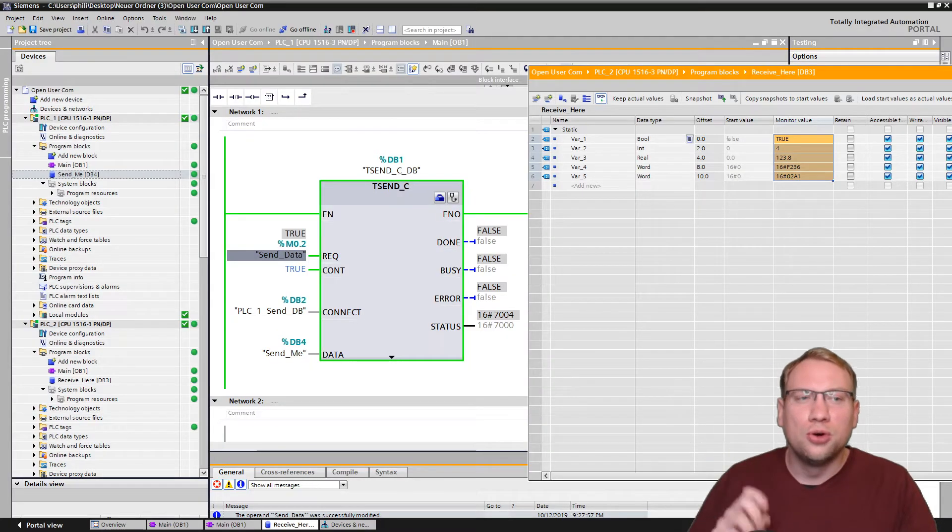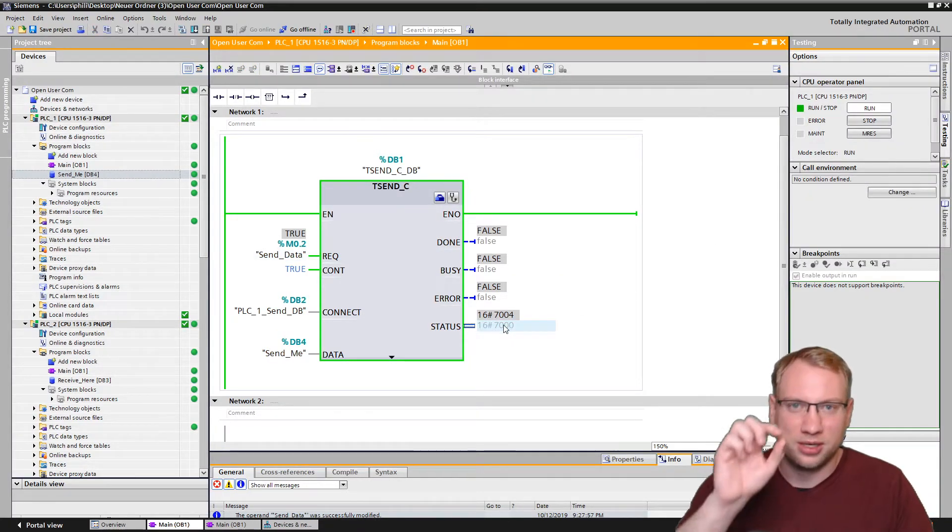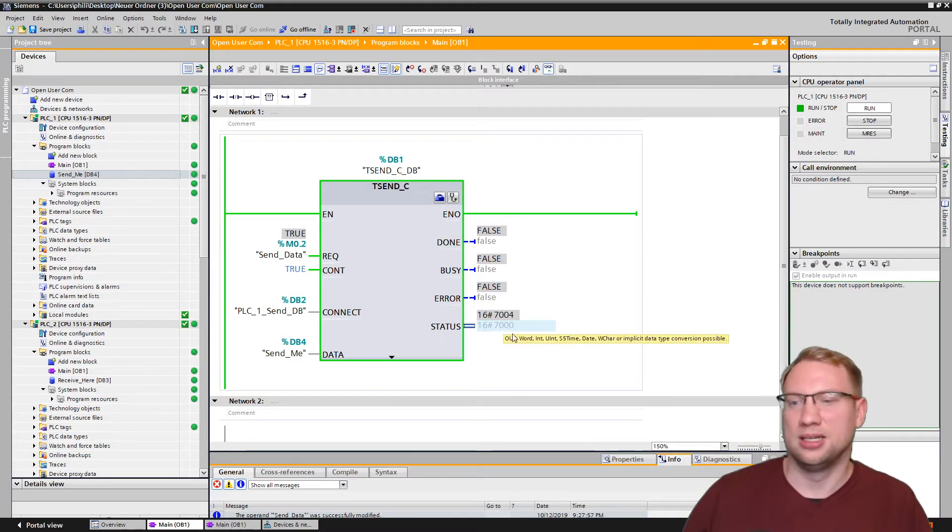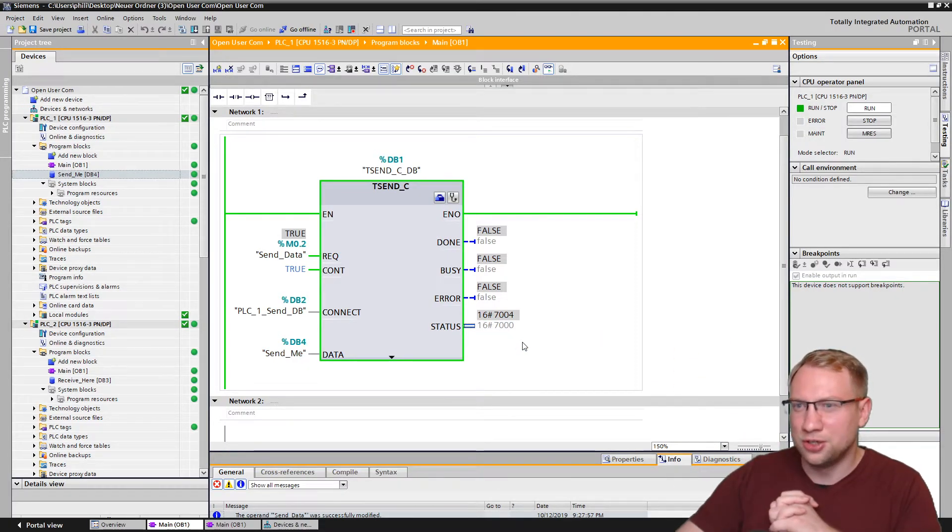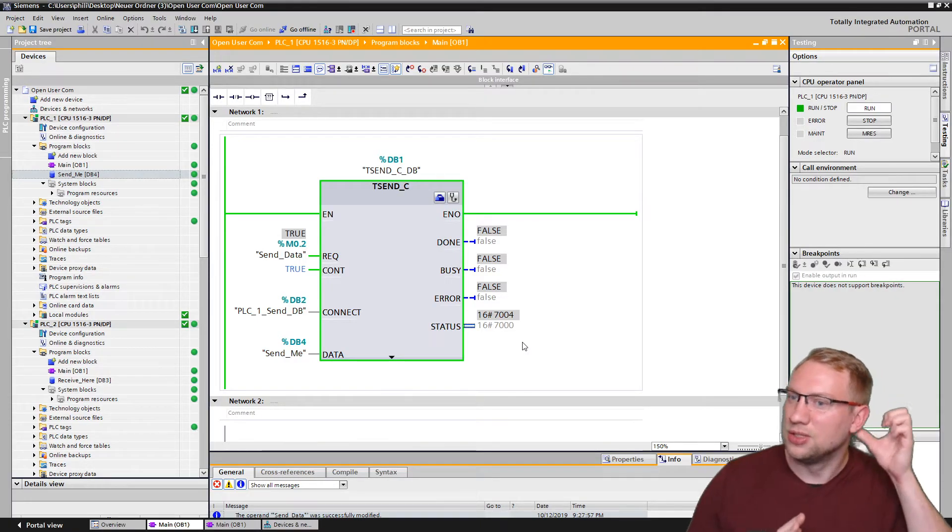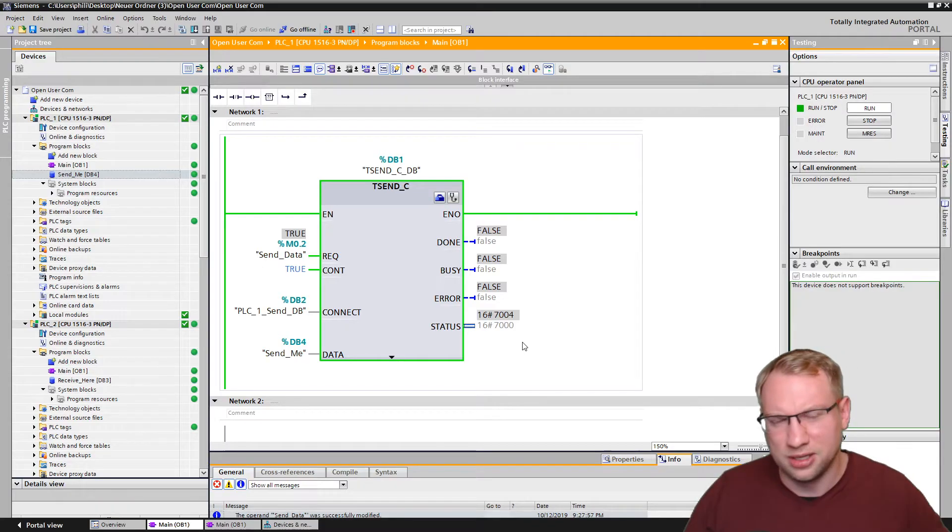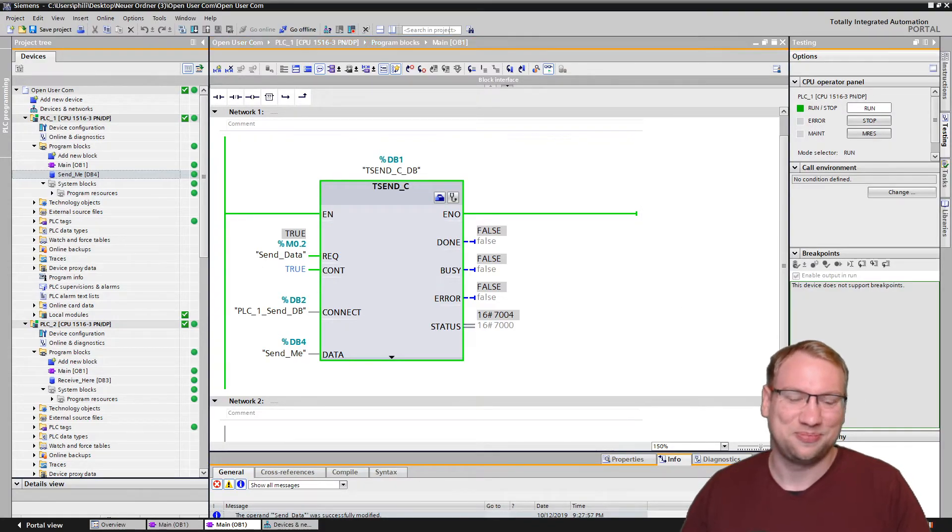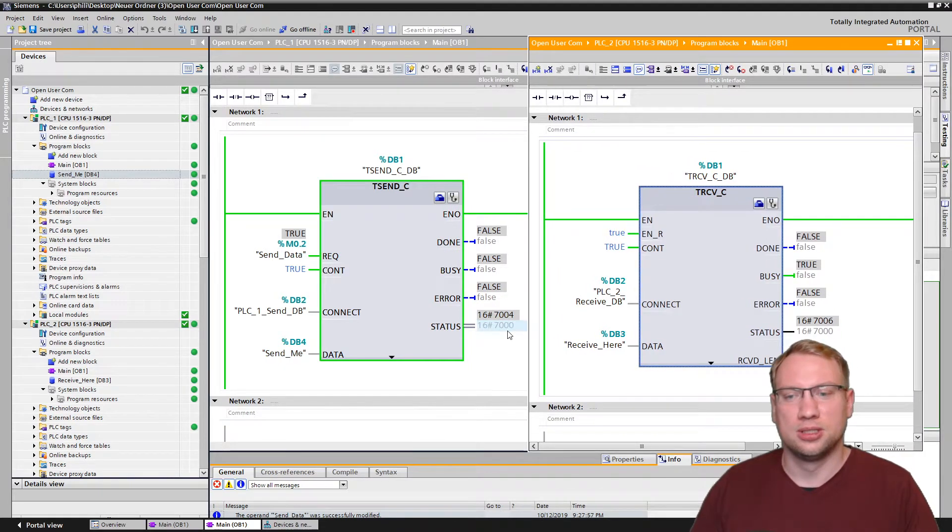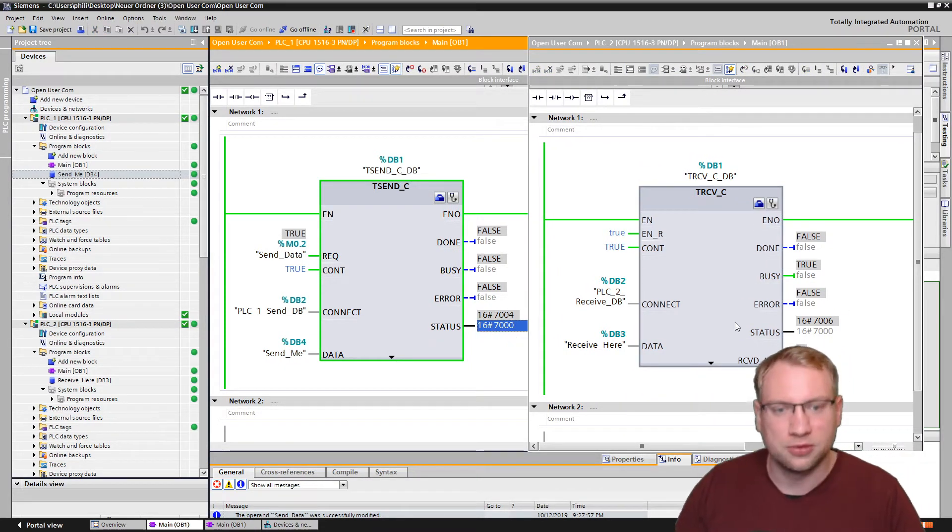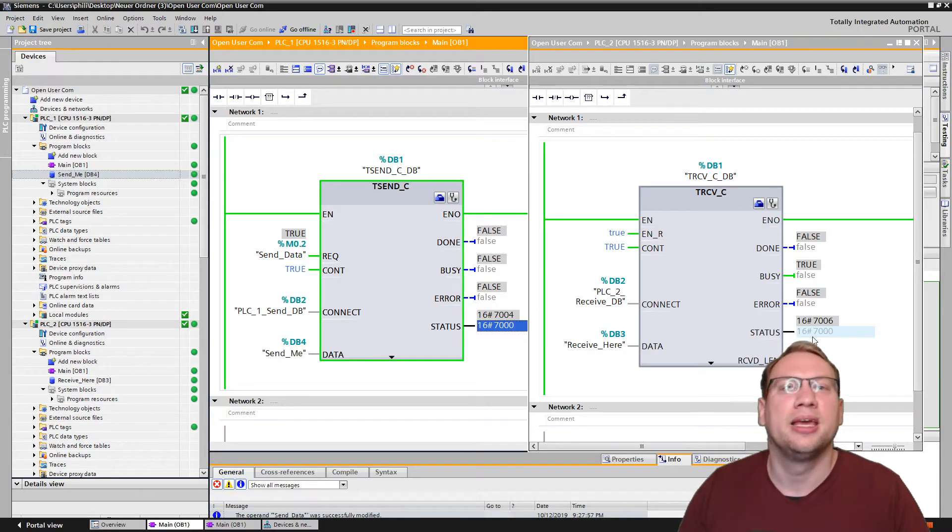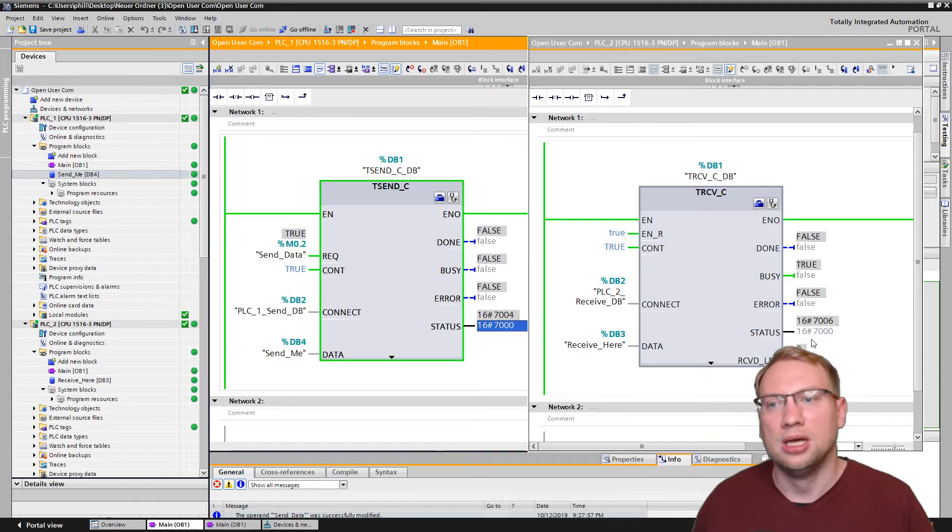What you couldn't see is that this value, very shortly, for like one cycle, it changed. Not even a cycle. This block is asynchronous, actually. So it's not really looking at the cycle times. So it's asynchronic. It doesn't matter what that is. I just throw it in there for those that were interested. Yeah, this is done. And you see those values are still the same. No job processing active, but active connection. And this one here says, hey, not receiving data because nothing is sent, but we have a connection.